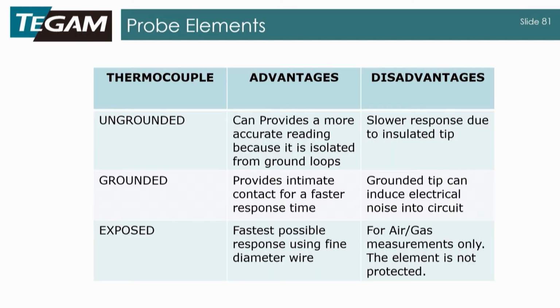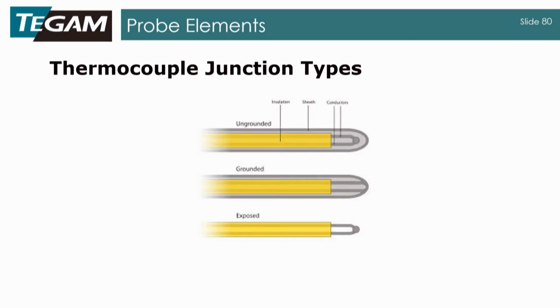So next I have a chart here giving you the advantages and disadvantages of each. For ungrounded, it's going to provide a more accurate reading because it's isolated from ground loops, but you do have a slower response because of that isolated tip. So whatever you're measuring is going to have to work its way through this area here to get to your thermocouple junction, while in this configuration, as soon as it touches your sheath, it's going to start measuring your temperature.